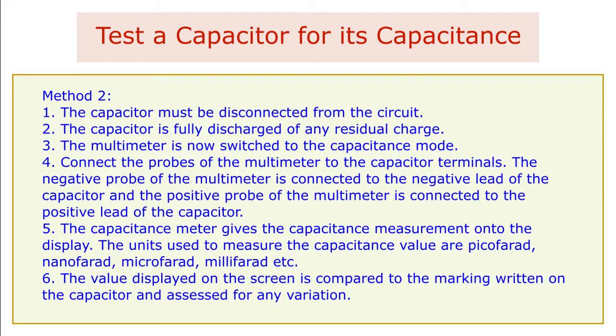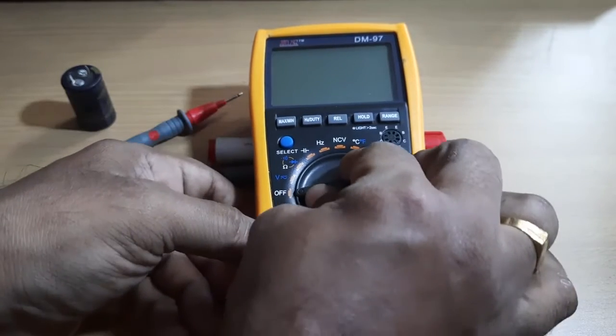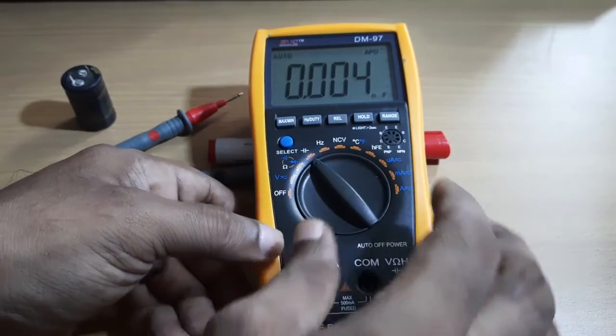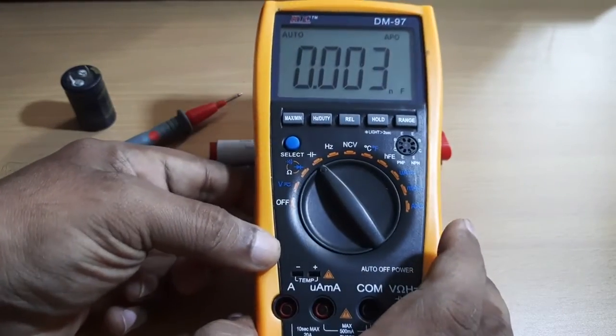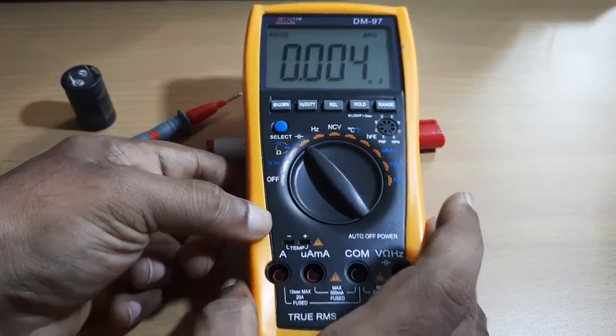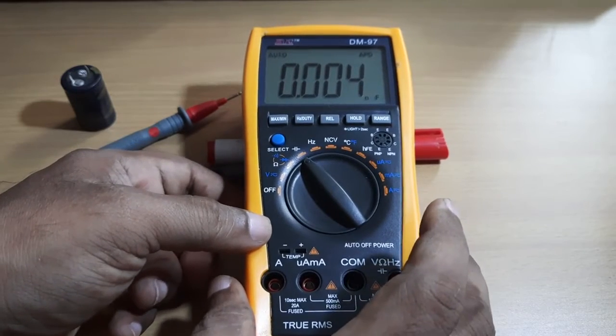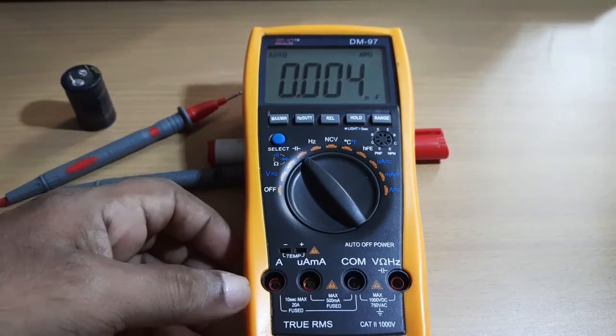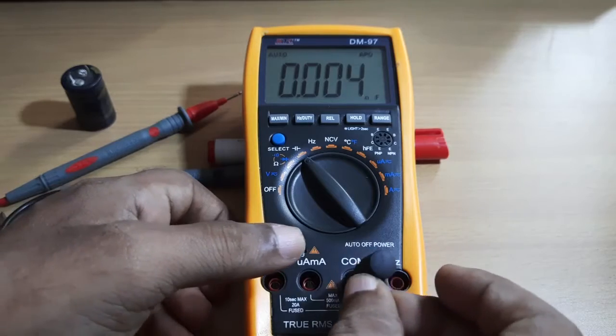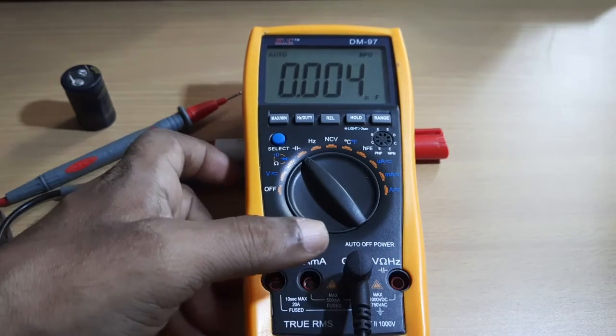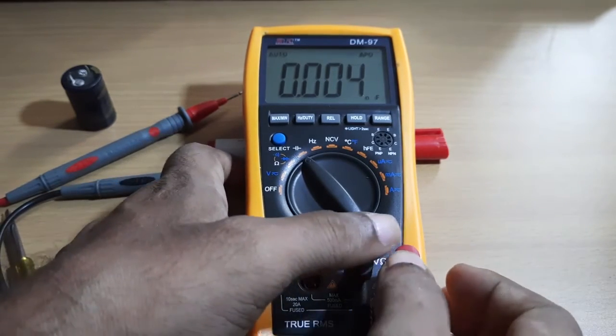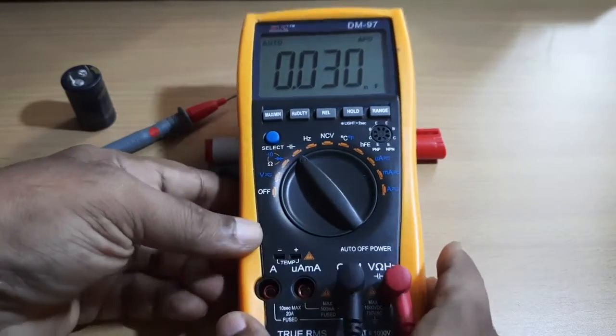This test is done with the following steps as given below. 1. The capacitor must be disconnected from the circuit. 2. The capacitor is fully discharged of any residual charge. 3. The multimeter is now switched to the capacitance mode. 4. Connect the probes of the multimeter to the capacitor terminals. The negative probe of the multimeter is connected to the negative lead of the capacitor, and the positive probe of the multimeter is connected to the positive lead of the capacitor.